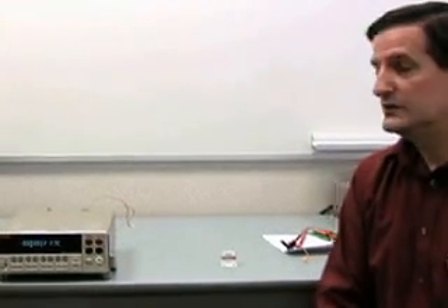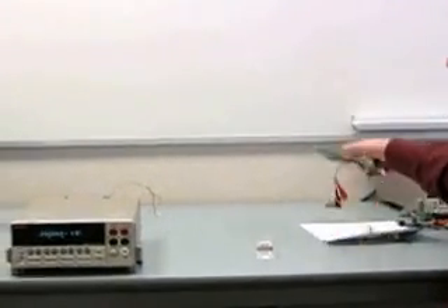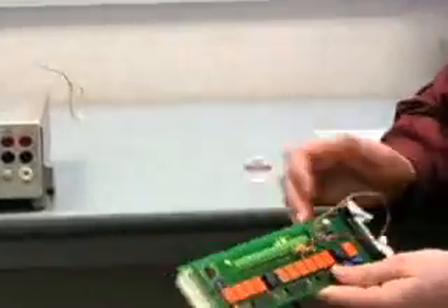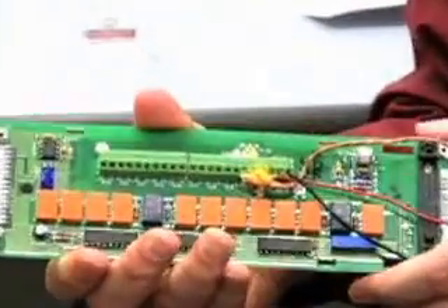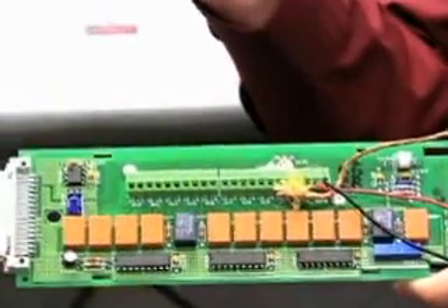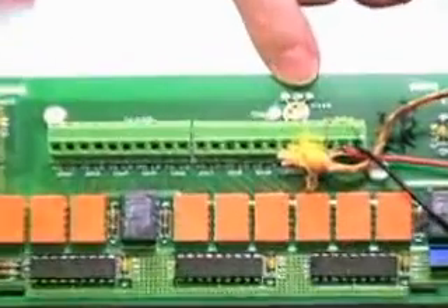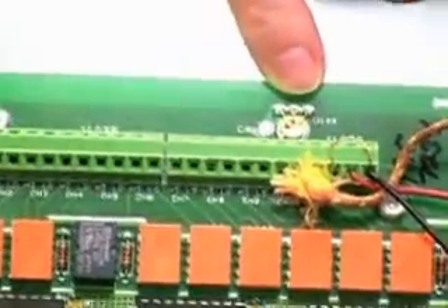This particular box will measure temperature with thermocouples. It can measure with type J, K, and T thermocouples. What you need is a little scanner card, something like this. It's 10 channels, and it has a cold junction compensation circuit on the card, right here. What that means is your linearization for your thermocouples is already taken care of for you. This takes up channel 1 on this 10 channel card. Let's take a look at that.